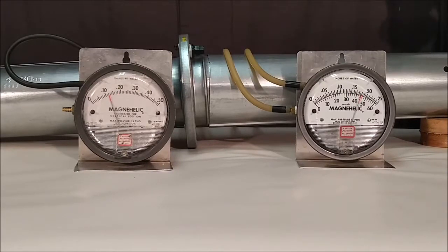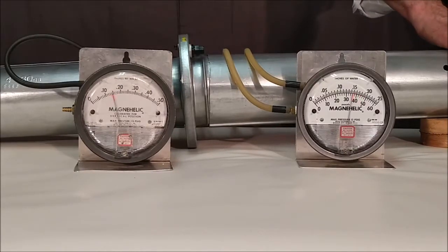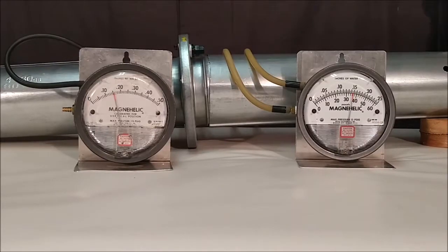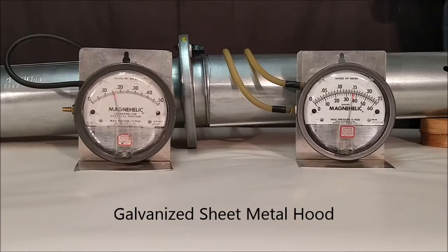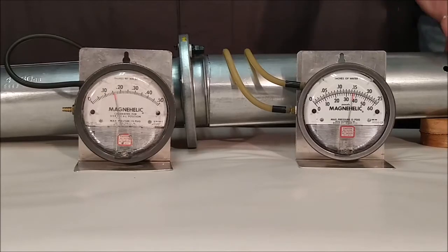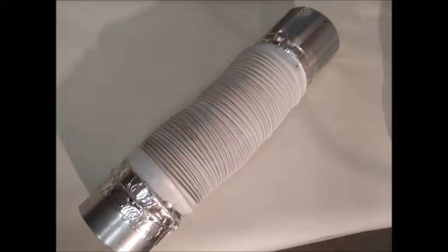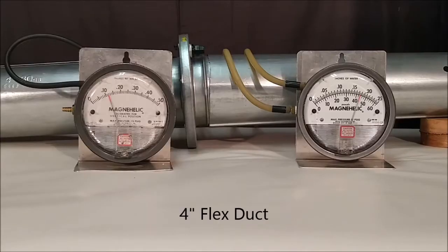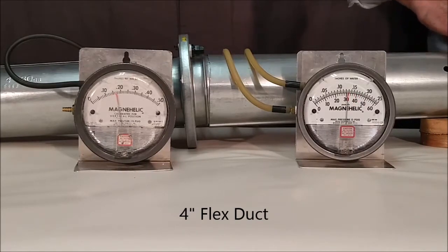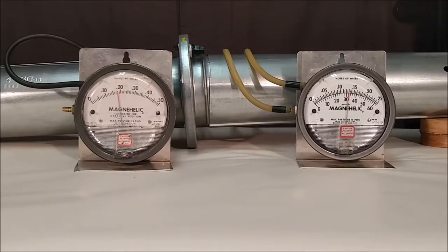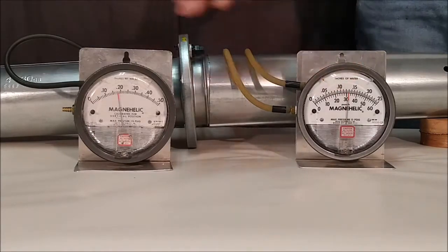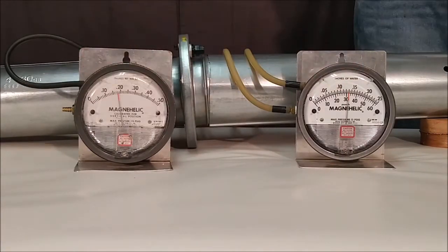Our next demonstration is our 4-inch galvanized sheet metal hood. Again, it has a measurable effect because the air is having to change direction to go through the hood and go through a screen. The third item is a piece of 4-inch flex duct. It's only 3 feet long, which is very short for the real world, but it's possible to see the drastic effect that it has, again, in diminishing the flow and increasing the static pressure. That's only 3 feet.